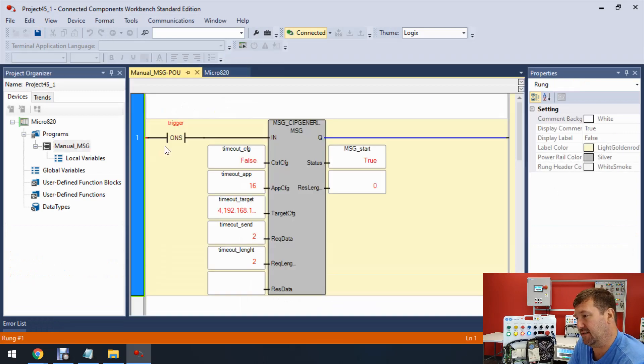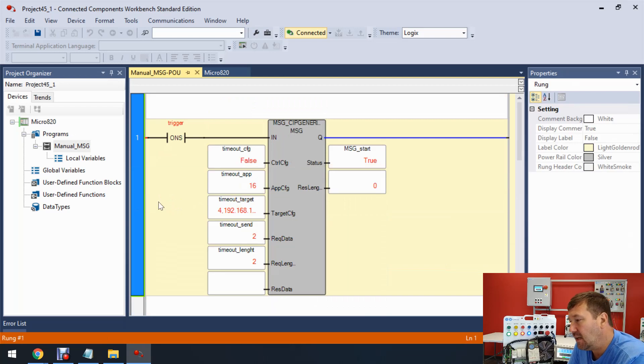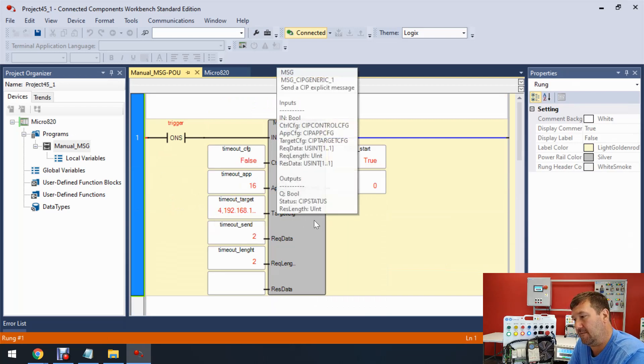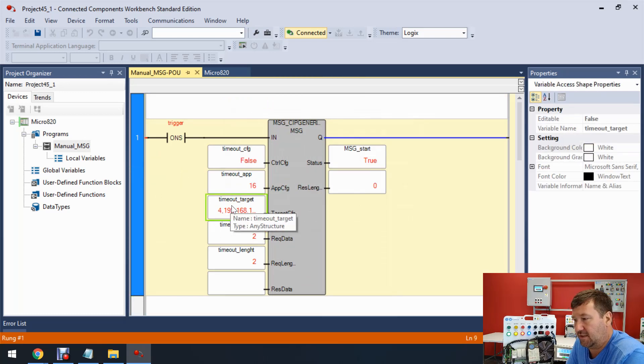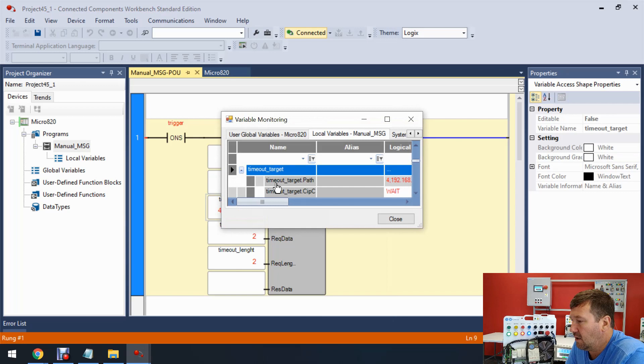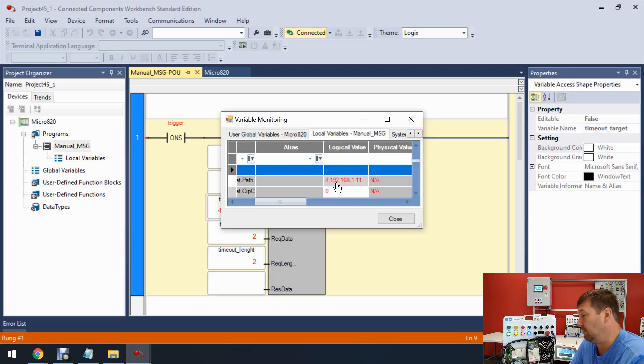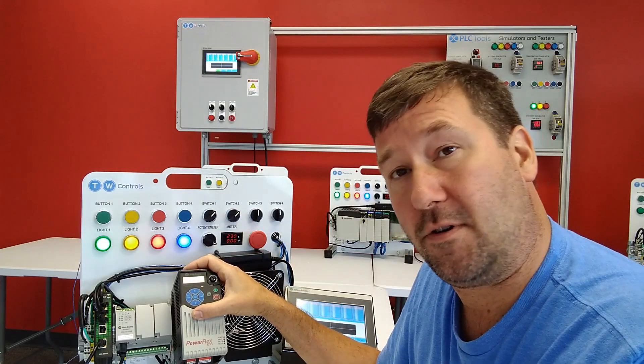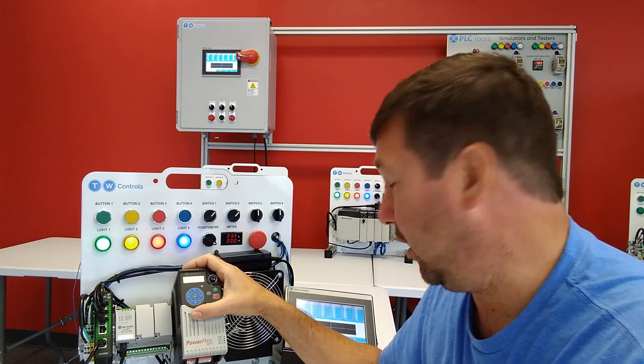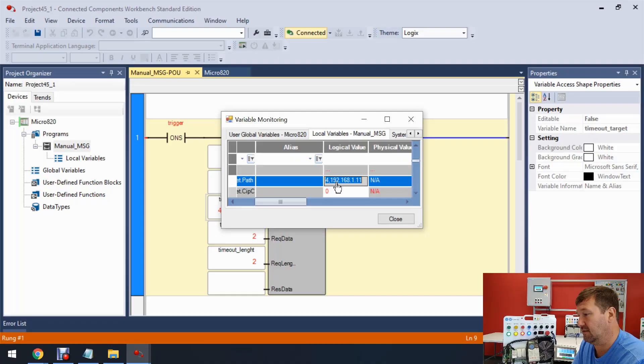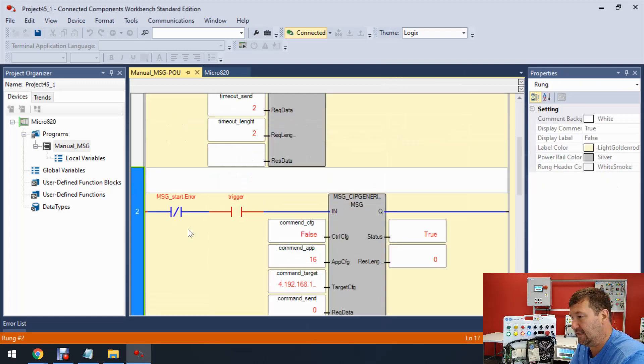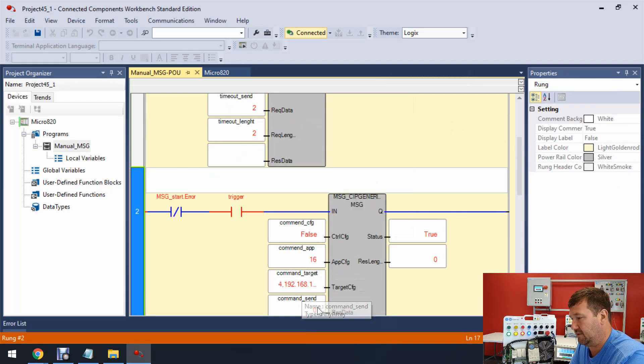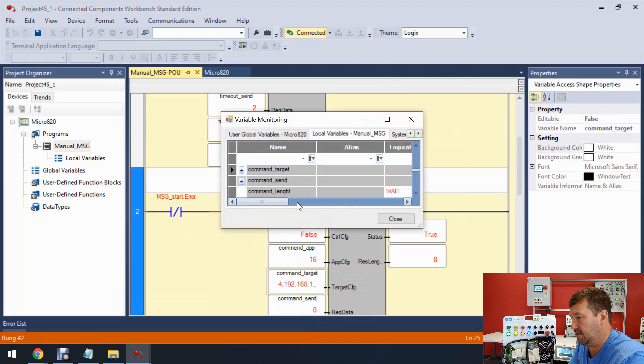So we have two message instructions. Rung one has a message instruction and rung two has a message instruction. And the one thing we'll need to look at is this target config right here of both of those. So just double click on the timeout target and let's open that up. And this target path right here, right now it's for 192.168.1.11. But our default IP address for our drive is 192.168.1.12. 11 is our HMI over here. So let's change this to 12. And then let's change this one, the second messenger instruction, also to 12.